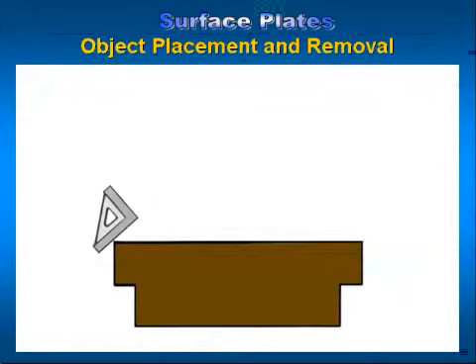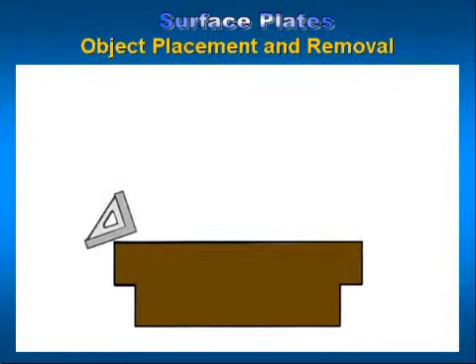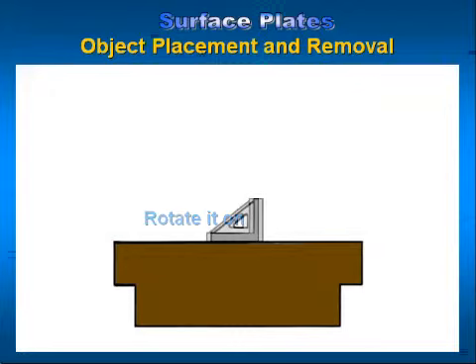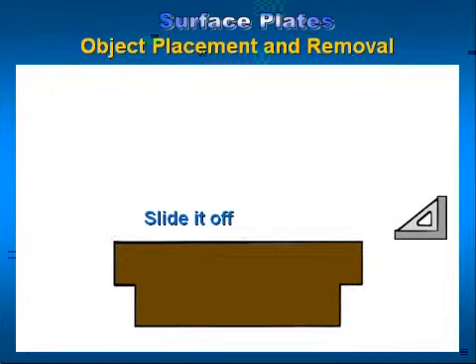Surface Plate Object Placement and Removal. When placing an object on a surface plate, bring the object to be placed on the surface to the edge of the plate and rotate the part up onto the plate. Then slide it across the plate. This will prevent damage caused by placing heavy objects directly on the surface and causing damage to the surface.